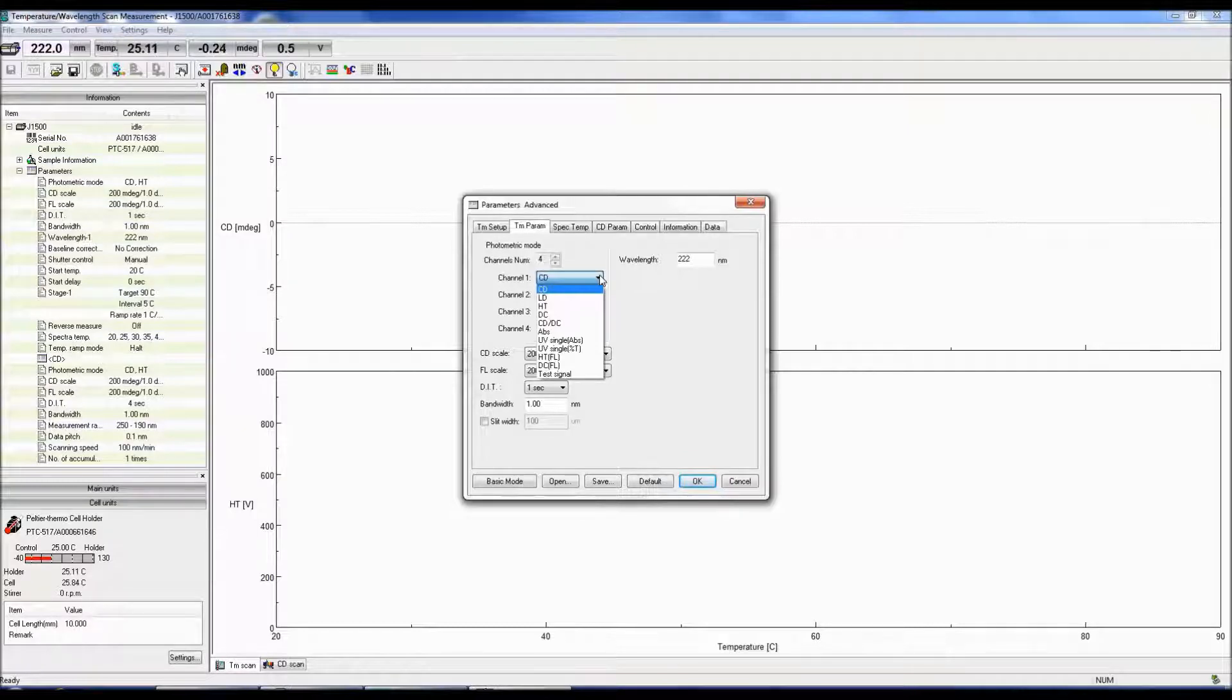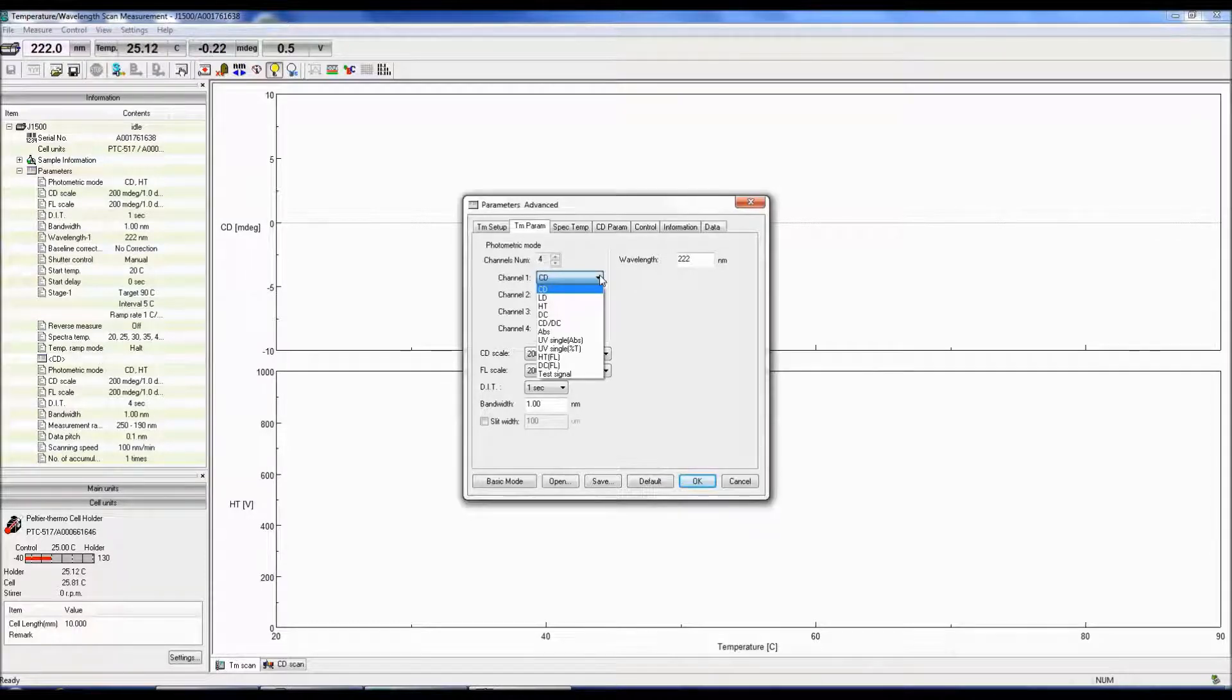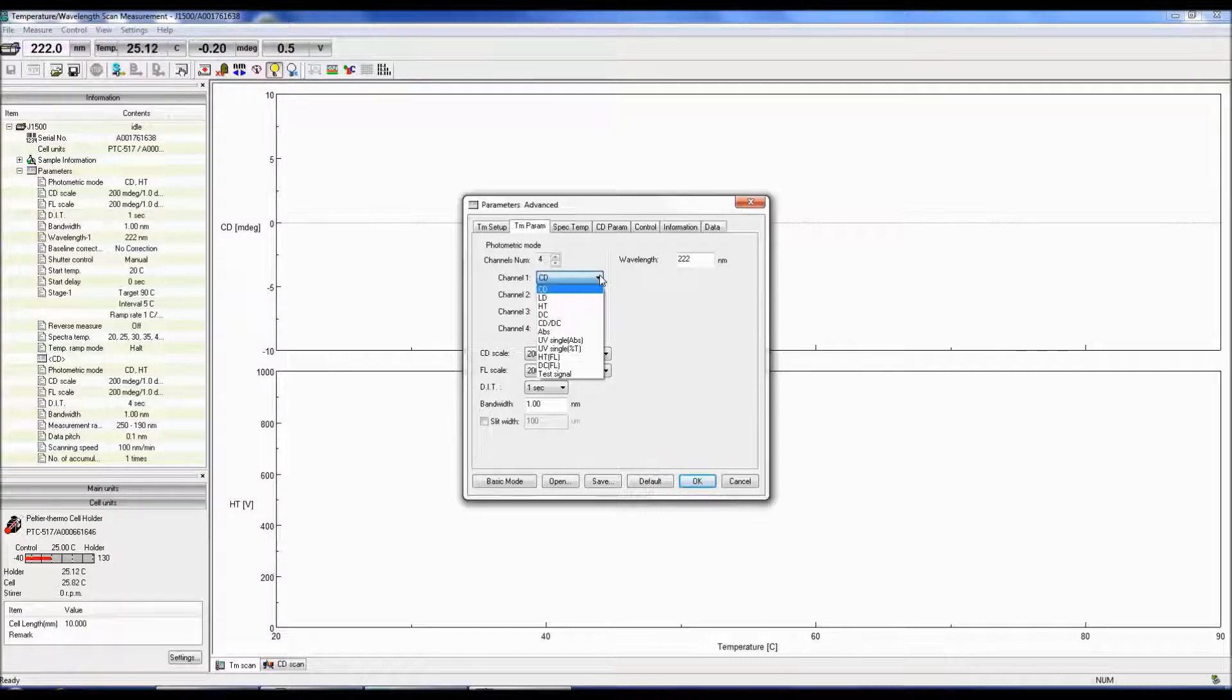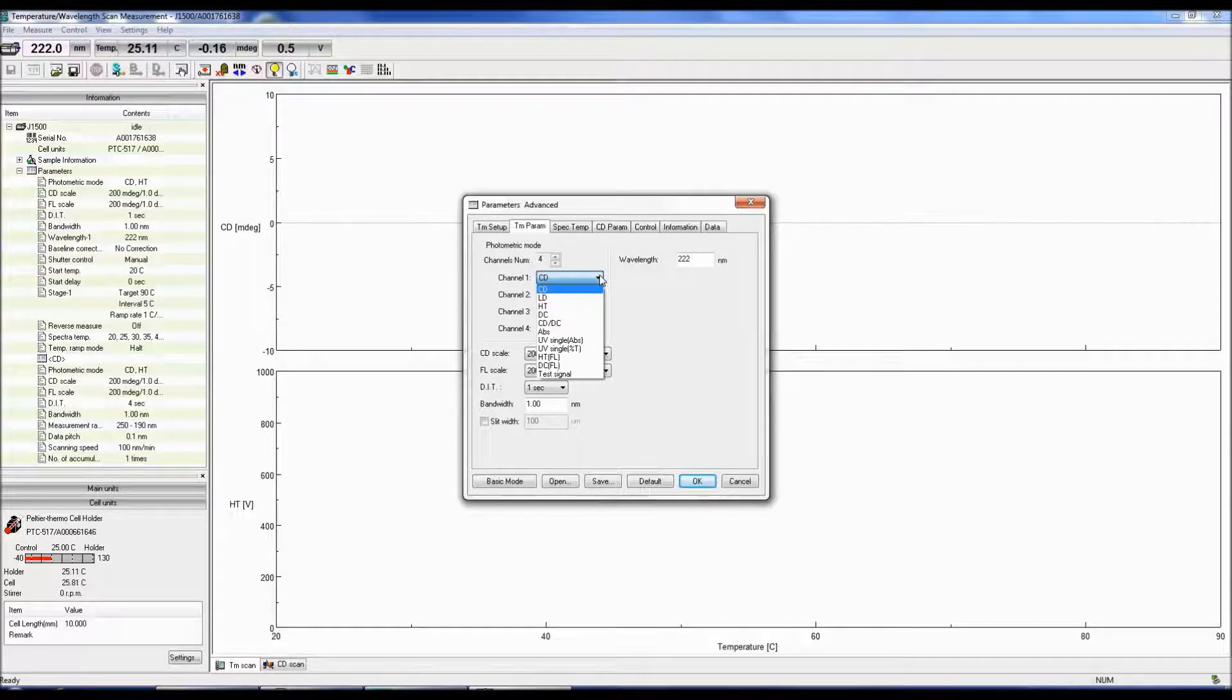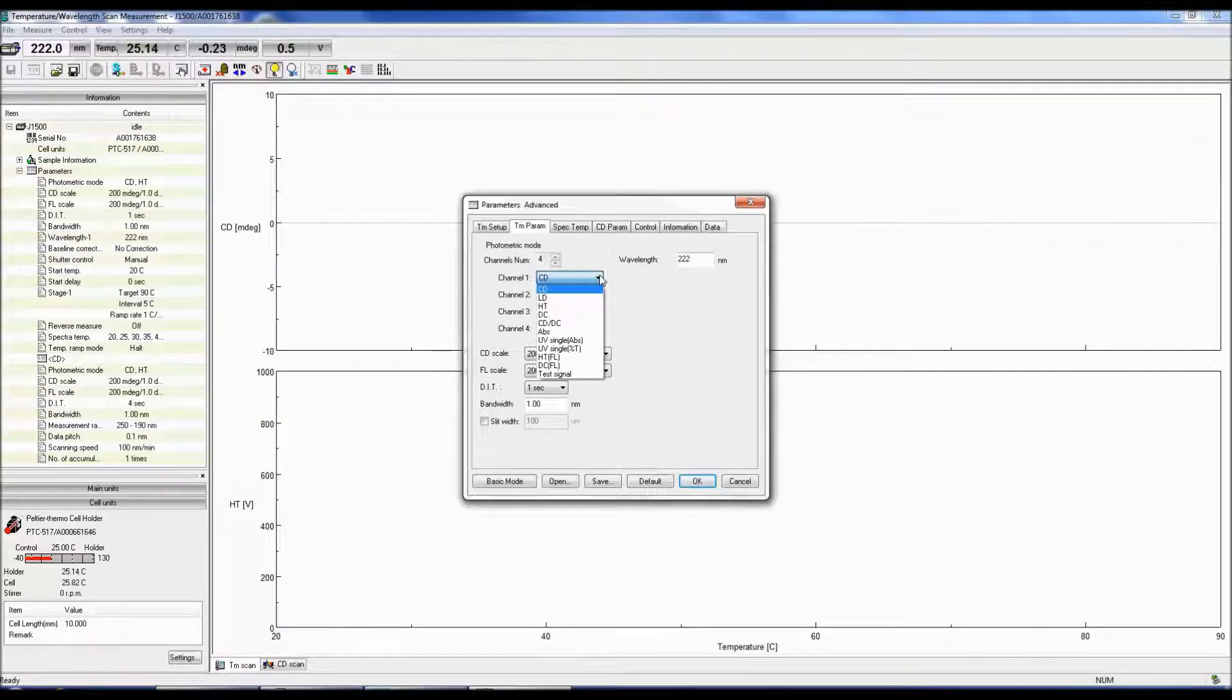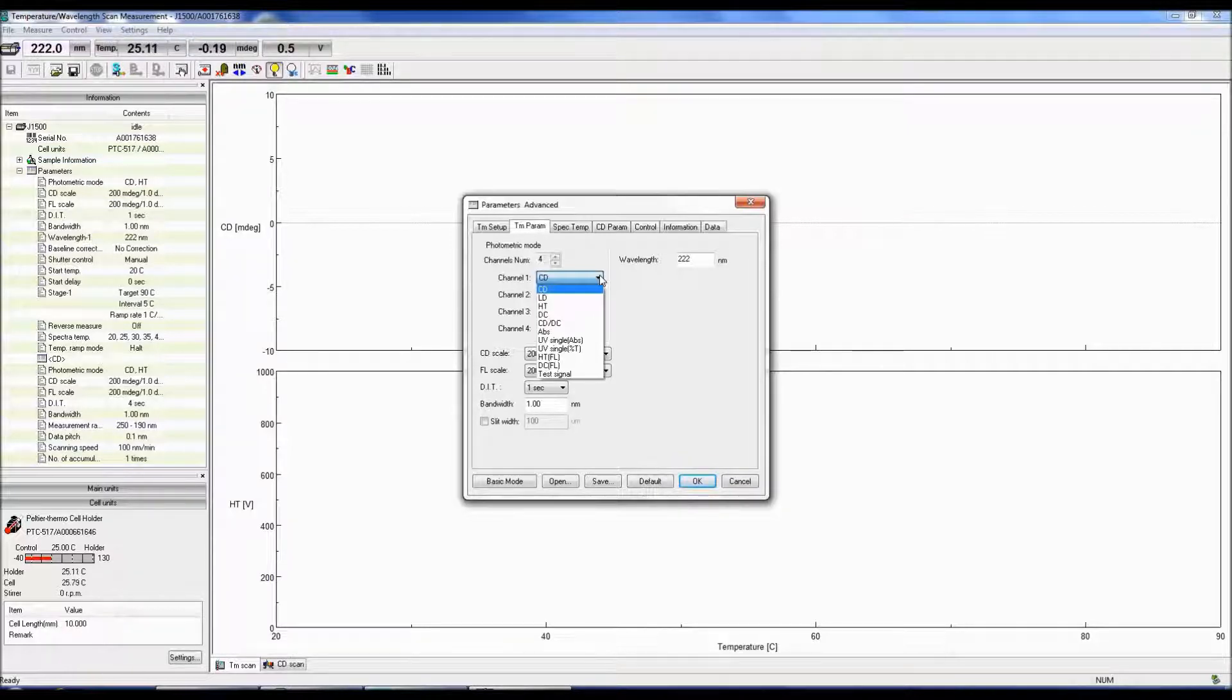Both the HT and DC modes monitor the photomultiplier tube voltage. HT is the high-tension voltage and controls the gain. Gain is the amount of current output for the number of photons reaching the detector. When a lot of light hits the detector, the gain and therefore the HT are low. The less light throughput, the fewer the photons reaching the detector, and the higher the HT and larger the amplification of the signal.